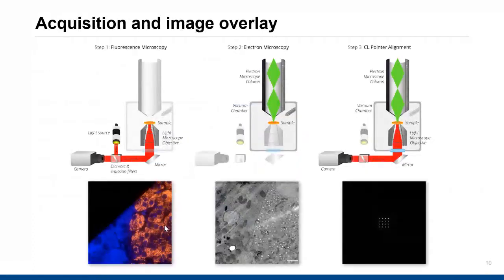The workflow schematically: the first step is fluorescence microscopy, where you have fluorescence generated by the sample giving rise to an image. The next step is electron microscopy, which is performed simultaneously — in the same system without moving the sample, without changing it in any way or adding contrast or new sample prep. The same sample is imaged using the EM, giving a high-resolution image showing the structure. After this, the alignment procedure is performed using cathodoluminescence, with the grid patterned on the sample.